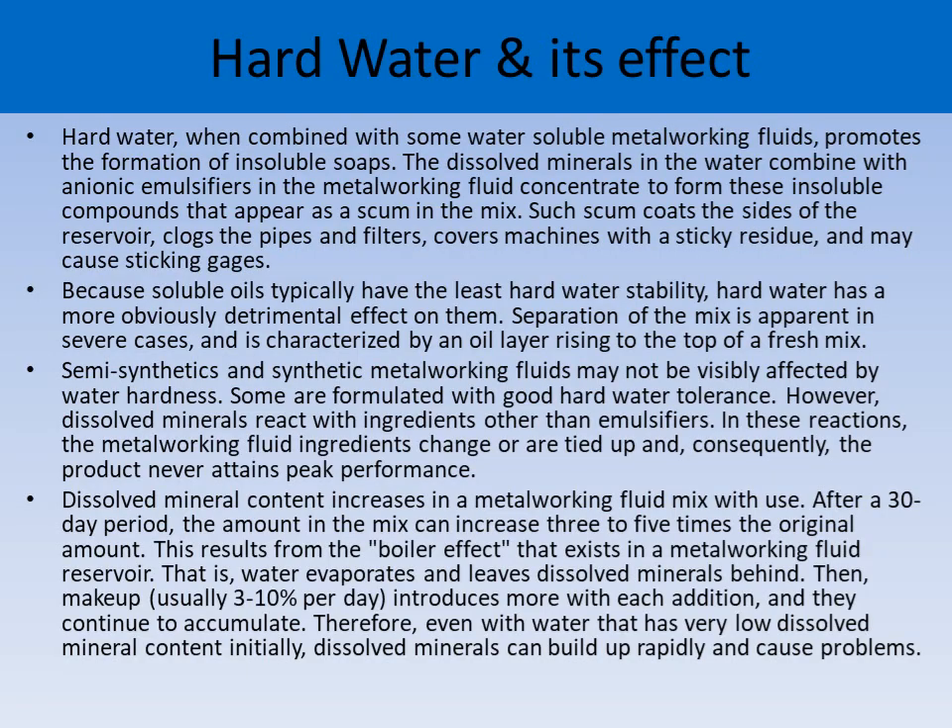Hard water, when combined with some water-soluble metalworking fluids, promotes the formation of insoluble soaps. The dissolved minerals in the water combine with anionic emulsifiers in the metalworking fluid concentrate to form insoluble compounds that appear as scum in the mix, clog pipes and filters, cover machines with a sticky residue, and may cause sticking issues. Because soluble oils typically have the least hard water stability, hard water has a more obviously detrimental effect on them. Separation of the mix is apparent in severe cases, characterized by oil rising to the top of fresh mix.